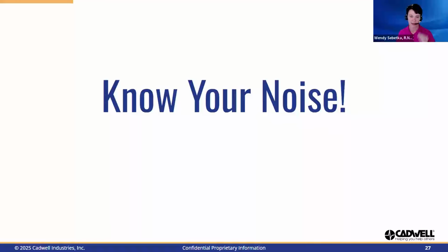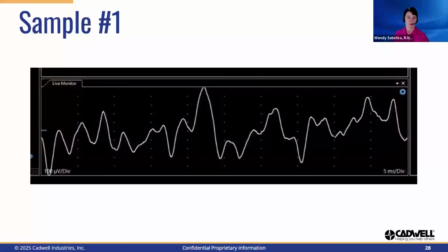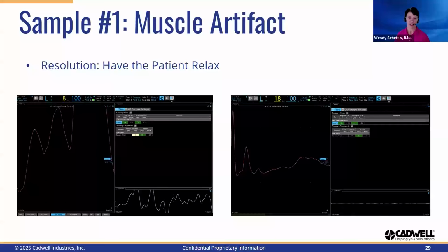Next, we will review some noise examples and work through some thought processes as we troubleshoot each scenario. When looking at sample number 1, I make note of the excessive unexpected deviations from baseline. The waves appear to be a bit disorganized. I don't really appreciate any spiky waveforms or a consistent sinusoidal appearance. These characteristics lead me to believe that this artifact is coming from a physiological source. Because of that, a review of my patient is performed. Patient was noted to be very tense and was asked to relax, and the baseline flattened out and the response was elicited. This issue was resolved by asking the patient to relax, and the better study was completed.